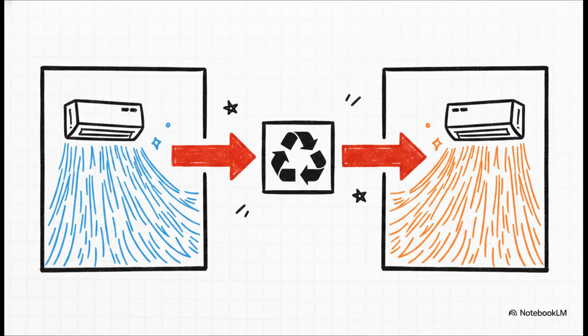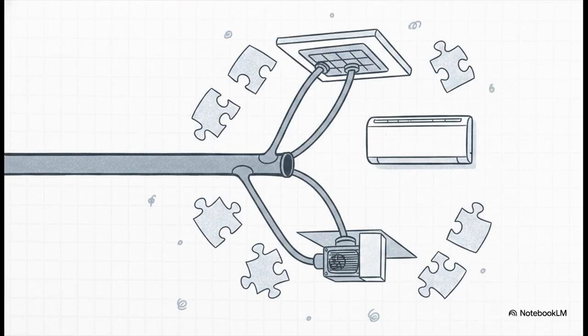Because the hybrid branch controller supports simultaneous heating and cooling, it unlocks a brilliant recycling story. You can literally take the waste heat recovered from a room being cooled and move it instantly to offset the heating demands in another zone. It acts just like an advanced traditional VRF system, but it does it entirely with water. From there, that heated or chilled water gets delivered straight into your specific zones.